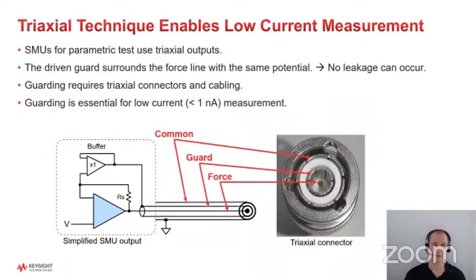I'm sure you're familiar with BNC type connectors, but you're probably not familiar with triaxial connectors unless you've done some parametric test work with source measure units. That's because SMUs always use triaxial outputs, since they need to measure low current. I'll explain that a bit better in the next slide, but as you can see in this simplified circuit at the bottom, there's a follower circuit. Whatever we're forcing, the driven guard, which is the center conductor, surrounds the force line, and then the common, the ground, is on the outside. Because that guard is always at the same potential as the force line, there can never be any current between the two. So there's no leakage, and that allows us to get very low level measurements, below a nanoamp. We can go down to femtoamp or even sub-femtoamp measurements using triaxial connections and cables.